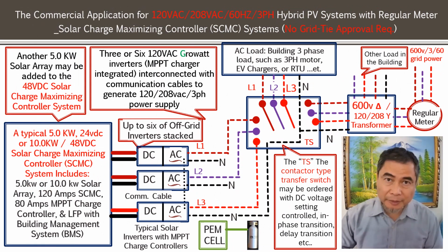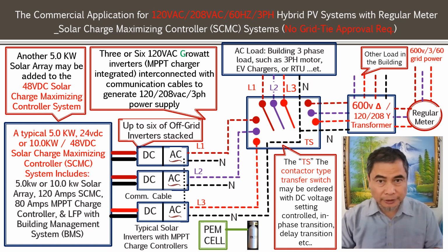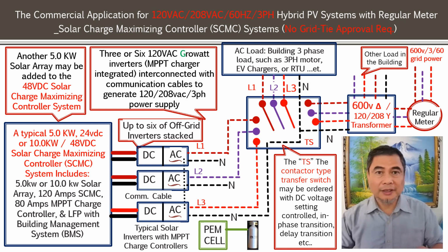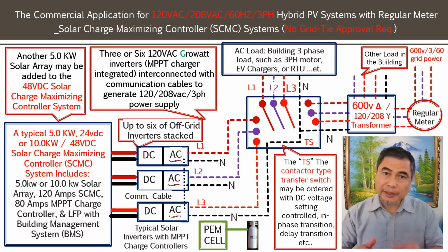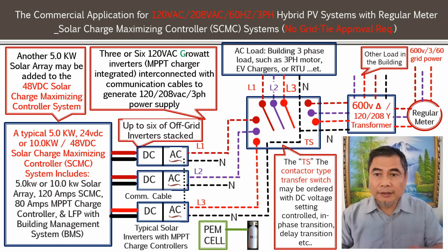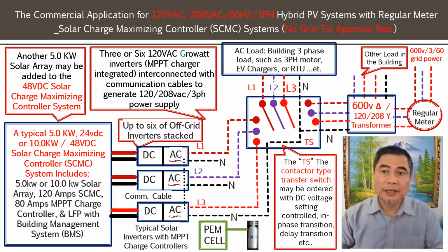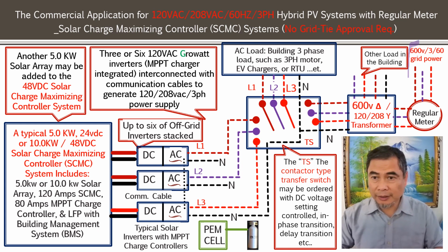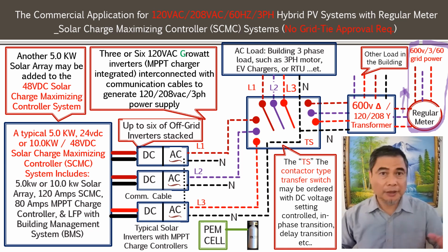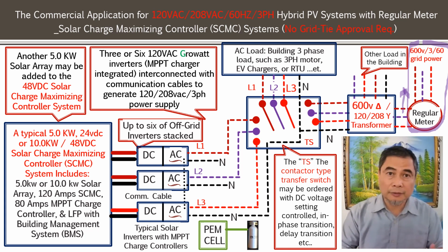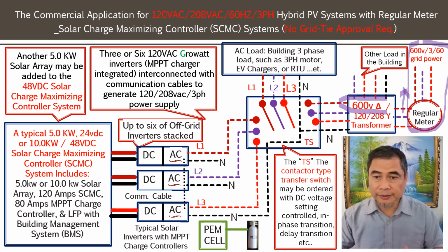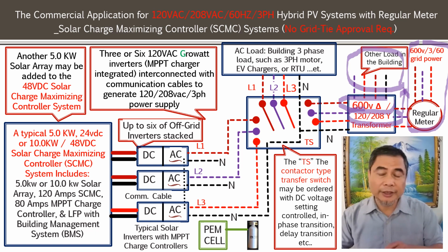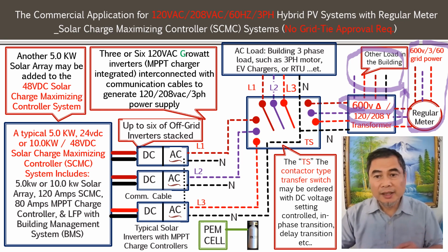This is a very typical application in commercial buildings, three-phase. So we have three-phase 120/208 wye connection in many commercial setups. You could have 575 or 600 volt, three-phase, 60 hertz coming to the building, and this is the typical commercial power supply to the building. You can have a 575, 600 volt system with appliances like a rooftop unit, and then you could have a step-down transformer to have a 600 volt three-phase delta, and it goes to a 120/208 wye connection transformer with a neutral, and then it will power the 208 wye connection system load, including maybe a rooftop unit or some other appliances.